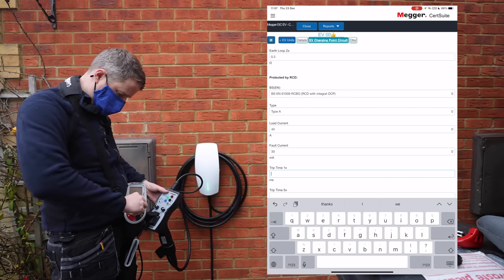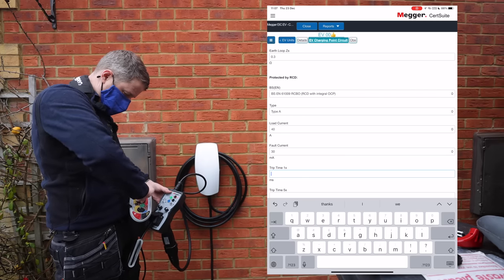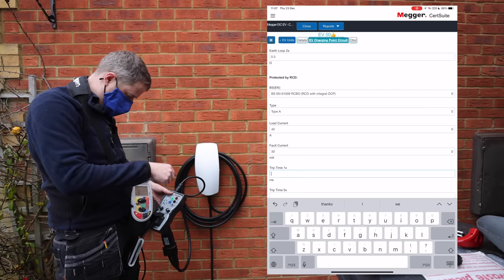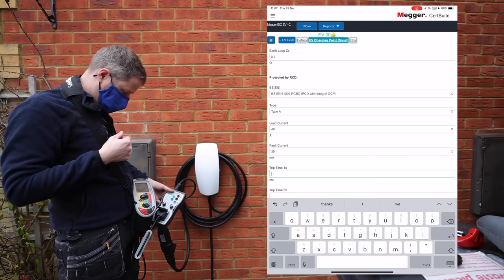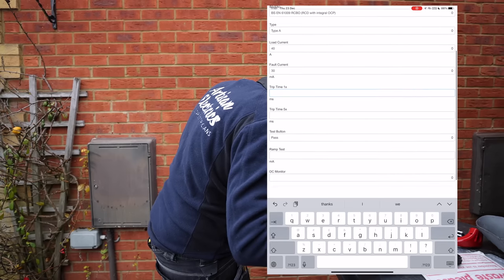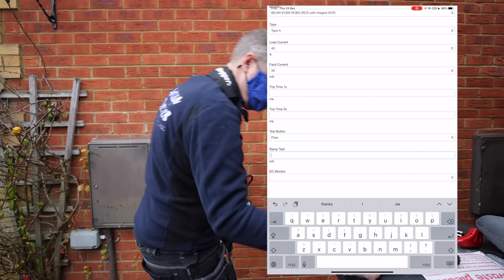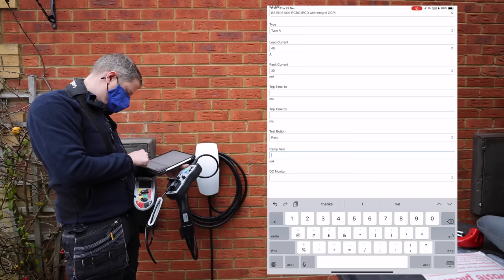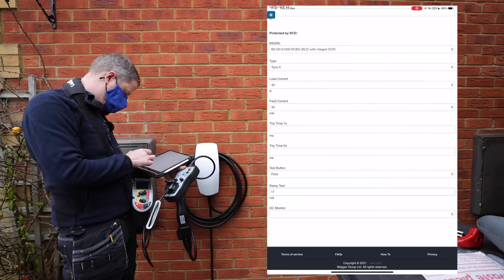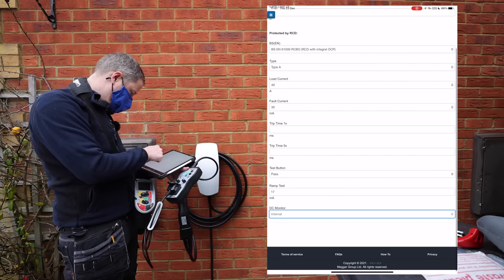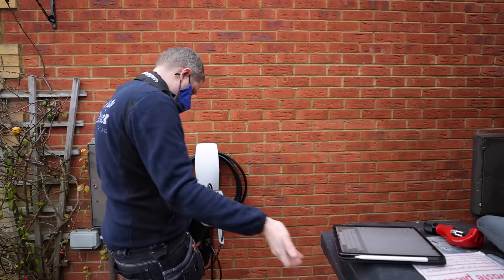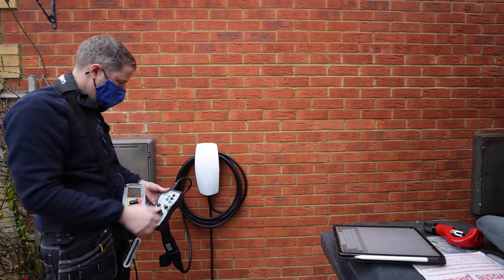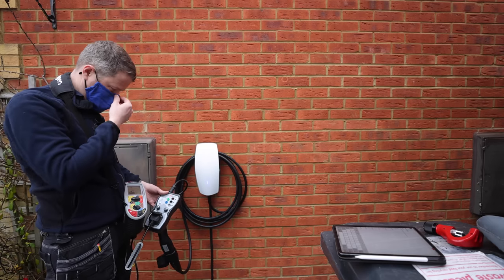So we've got 0.3, so what we'll do then is we'll put that into our iPad. We'll put 0.3, and that's all good. So we've passed the PE test, we've passed the PE error, passed the CP error, so that's all good. And now we've just got to do our RCD trip times. So hopefully Lee will reset the RCD inside. So we'll put it on 30 milliamps auto, we'll do a ramp test first. And that's tripped at 17 milliamps, which is perfect.